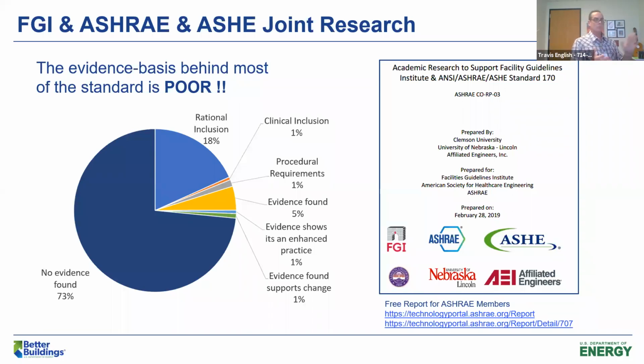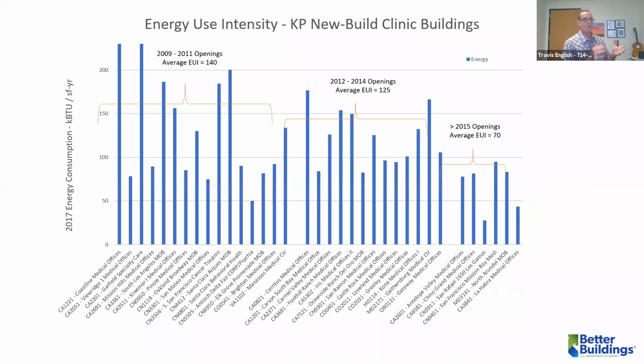Let's hit the next slide, because I want to show a couple years' worth of buildings leading up to this one. Most of our new construction in the last 8 years has been these clinic facilities, and starting in 2011 we've had a pretty aggressive energy program around them. We do energy models for every building and have an energy target for outpatient clinics - 50 EUI, the design energy target. We measure the result of every building and compare it to the model. You can see this dropping curve: buildings opened from 2015 to 2017 and on, compared to those opened around 2012 and prior, show a full 50% reduction in energy signature.